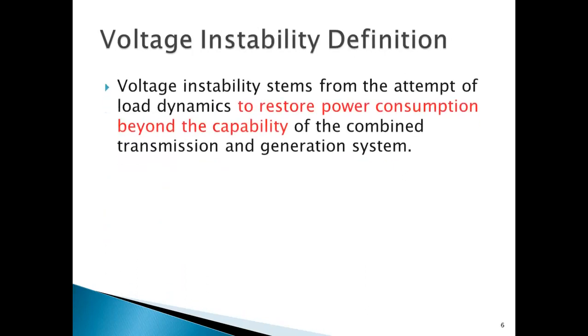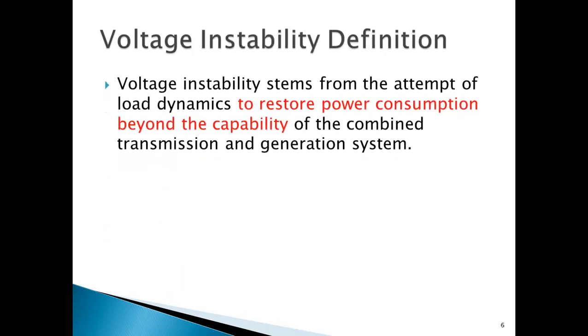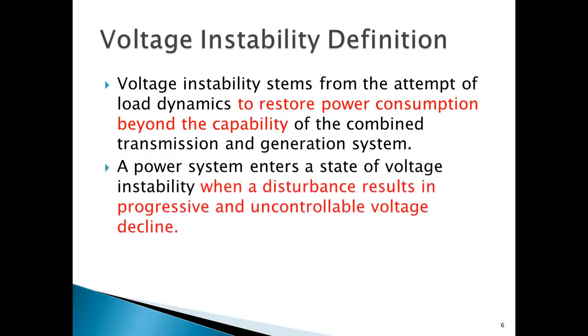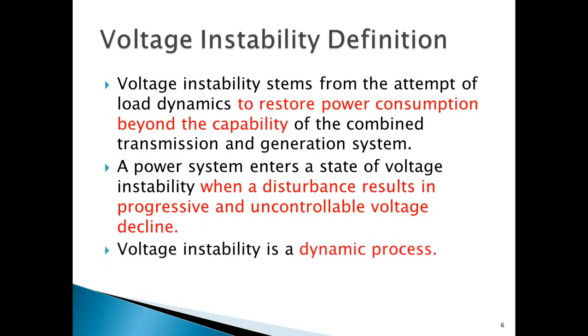How is voltage instability defined? Voltage instability stems from the attempt of load dynamics to restore power consumption beyond the capability of the combined transmission and generation system. A power system enters a state of voltage instability when a disturbance results in a progressive and uncontrollable voltage decline. The main symptom of voltage instability is low voltage. Voltage instability is a dynamic process as the voltage varies depending upon power system loads from time to time.